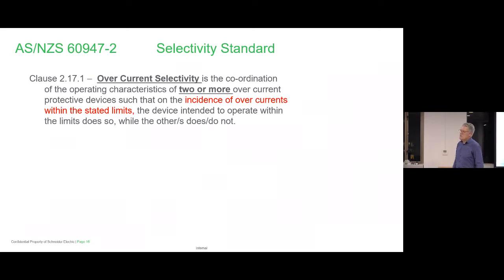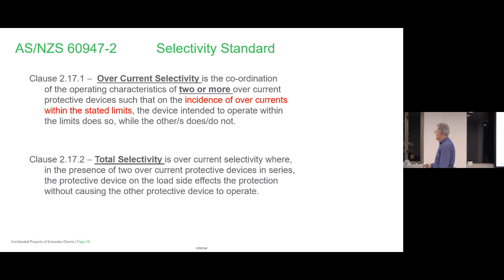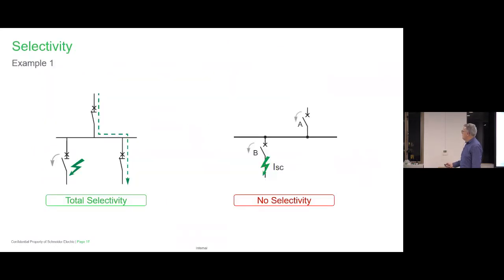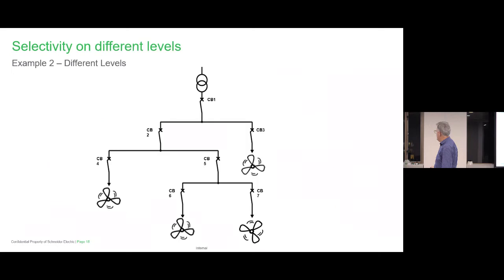They're not just talking, because we always say, oh, well, if there's no total, that's hopeless. Well, please don't think that, because it's not necessarily true. And then we have a statement there for total selectivity. So they have covered both elements, which is nice to see. This is a way of looking at it. That's pretty obvious, isn't it? It's very simple. You can see why that's total selectivity on this side, because this one hasn't. This one's open, this one's closed, and this one is both opening, A and B.